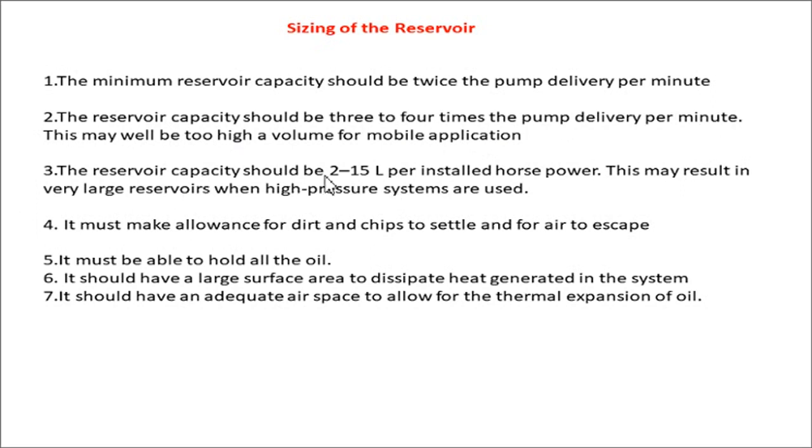The reservoir capacity should be 2 to 15 liters per installed horsepower. This may result in very large reservoirs when high pressure systems are used.